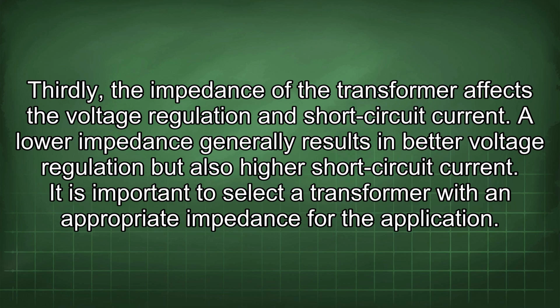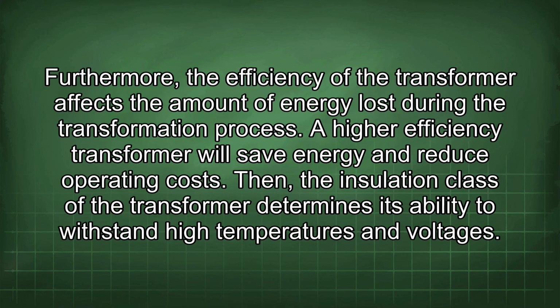Thirdly, the impedance of the transformer affects the voltage regulation and short-circuit current. A lower impedance generally results in better voltage regulation but also higher short-circuit current. It is important to select a transformer with an appropriate impedance for the application. Furthermore, the efficiency of the transformer affects the amount of energy lost during the transformation process. A higher efficiency transformer will save energy and reduce operating costs.